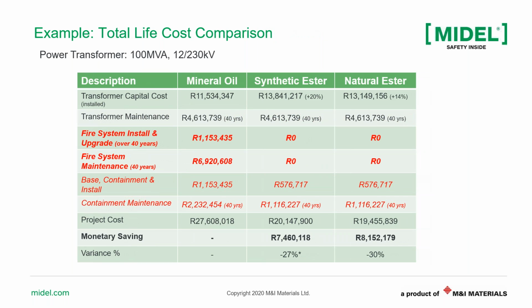Another example here for a power transformer. Again, in a power transformer, the initial cost of the transformer for a synthetic ester can be 20% more than a mineral oil. Natural ester can be 14% more than a mineral oil. But for these big units, usually you can get rid of certain installations like the fire suppression system and the space of the substation, so reducing cost there. Also, the maintenance of the fire suppression system for 40 years can be reduced when you are using an ester, and the base containment. So overall, you can achieve actually lower cost than a mineral oil, by 27% reduction with synthetic ester or 30% reduction with natural ester.